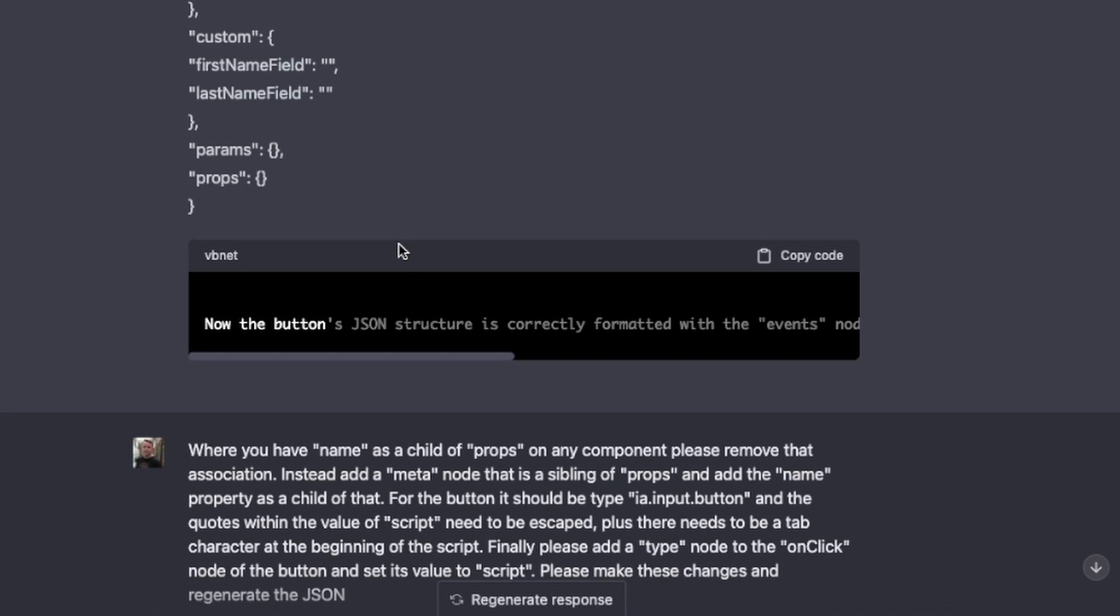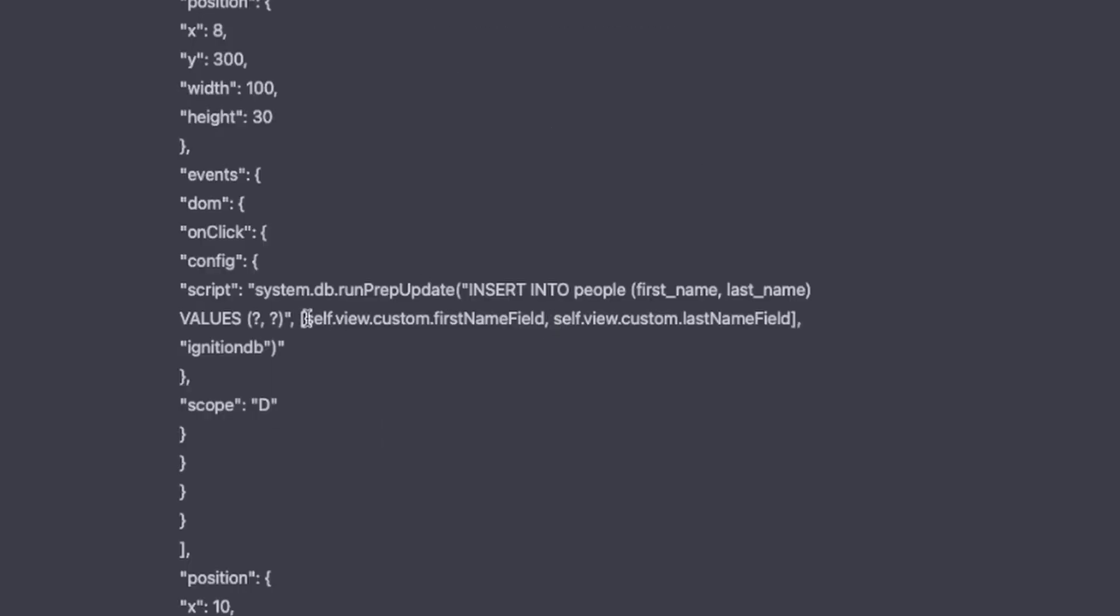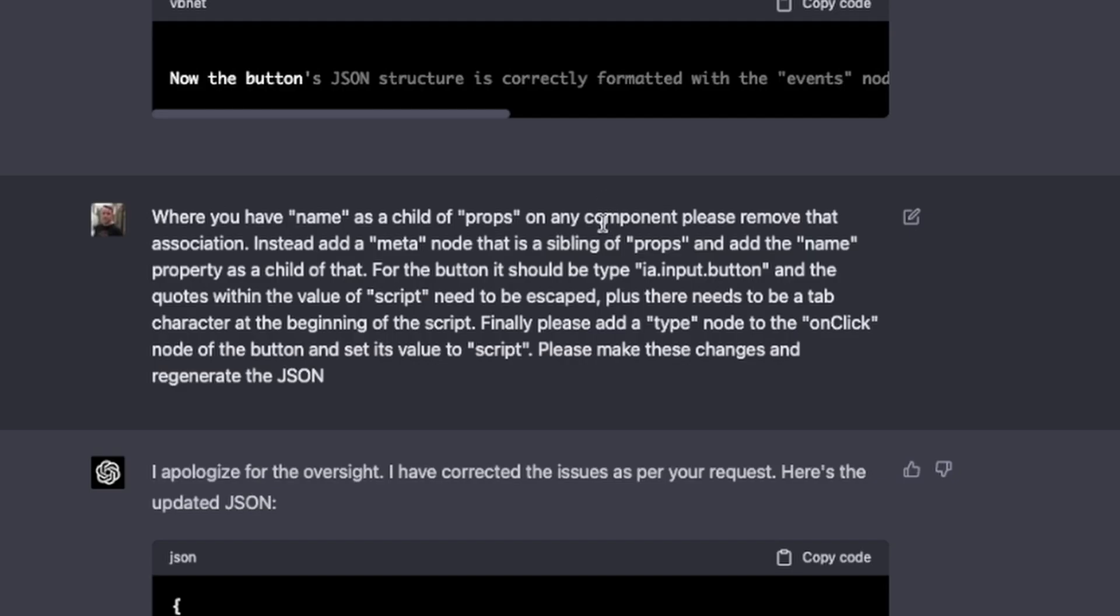So we compare that and we see if that imports and we get some problems there because we're trying to look at self.view.custom.firstname field and last name field. And those are not bound to anything because we haven't told it to bind those to anything. Also, what we're going to find here is it has a name value as a child of props on each of the components. It's not under the meta node like it needs to be. So when we're trying to do a find of that component of the text field or the text field underscore zero, like it's called them in the tree, it doesn't find those because they're named something else. So we're going to tell it to fix that.